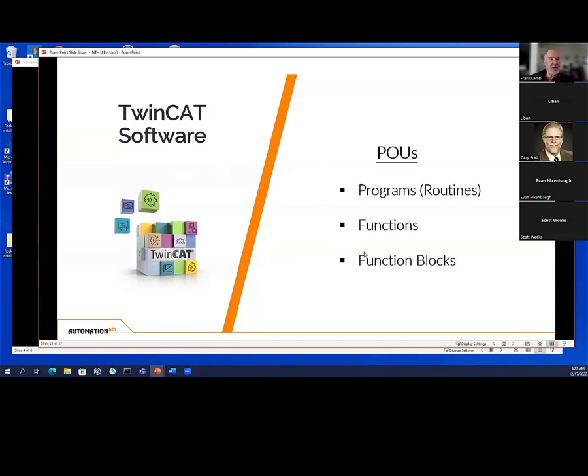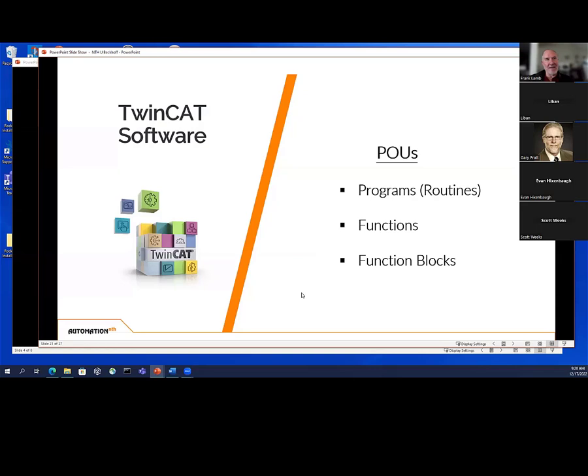We will be going through POUs — Programming Organization Units. For those used to routines, tasks, and function blocks in Allen Bradley or Siemens, that's what POUs are. It's not a term you hear in Allen Bradley or Siemens or GE — you'd call them routines or programs. But this is what they're called in Beckhoff. We use programs rather than routines — they're about the same thing — and then functions and function blocks.